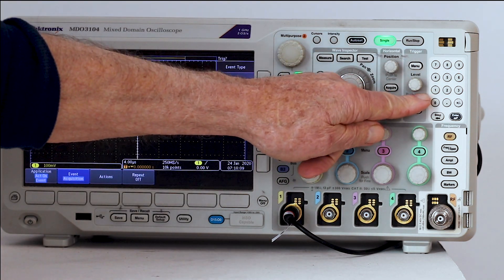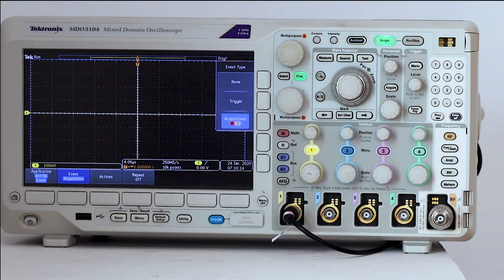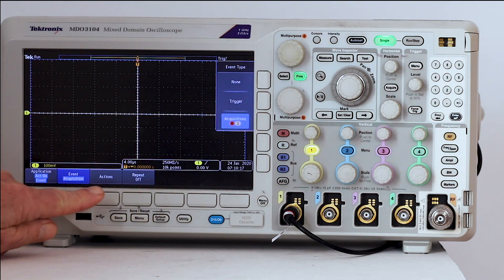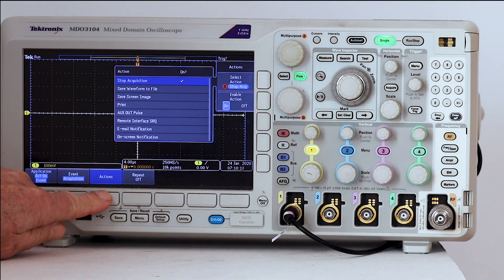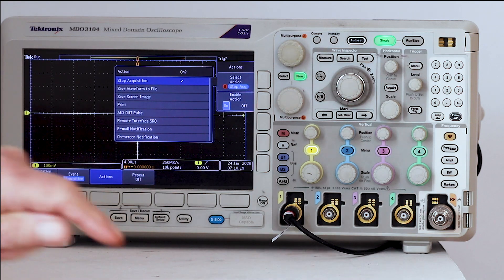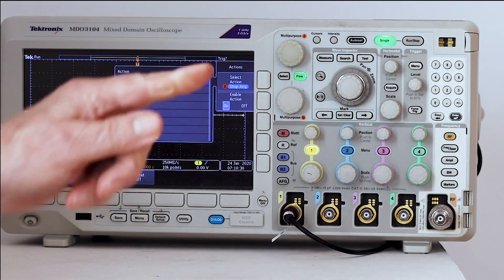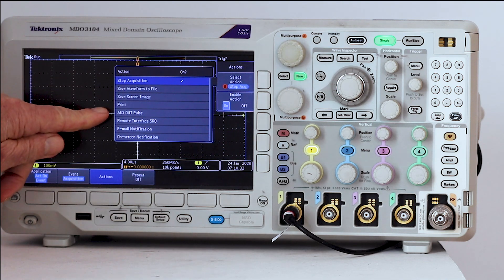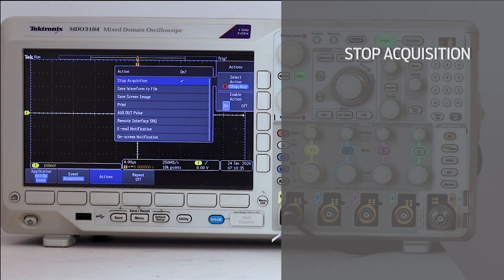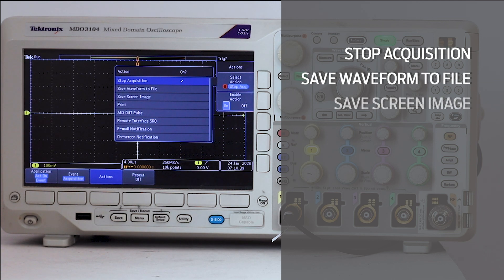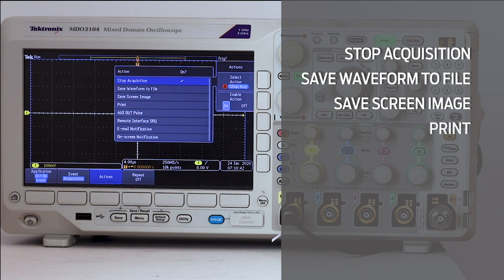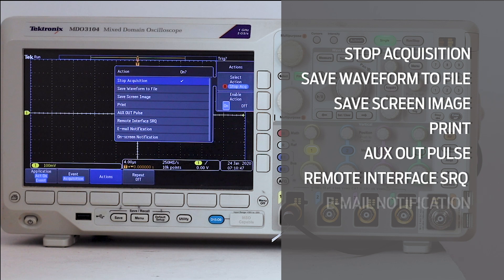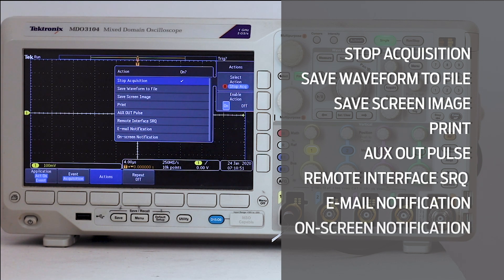Going back to the horizontal menu, the next menu choice is actions. Pressing the associated soft key, we see that any of the eight actions can be selected by turning multipurpose knob A. They are stop acquisitions, save waveform to file, save screen image, print, auxiliary out pulse, remote interface SRQ, email notification, and on screen notification.